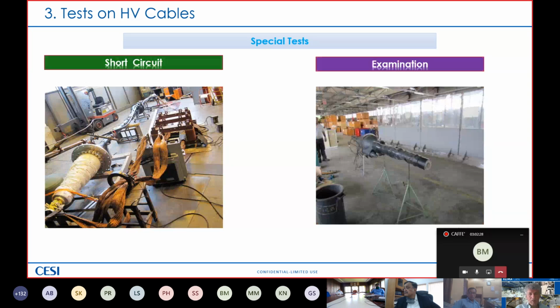Then a short circuit test, of course, this is more normal for our electrotechnical understanding. For example, this test was performed for a Middle East utility in Milan on a 400 kV cable connection. They wanted to verify the connection that was designed up to 40 kiloamps, as far as I remember, 1 second. These accessories can withstand this short circuit situation in order to prevent problems during the real installation of the cable system.